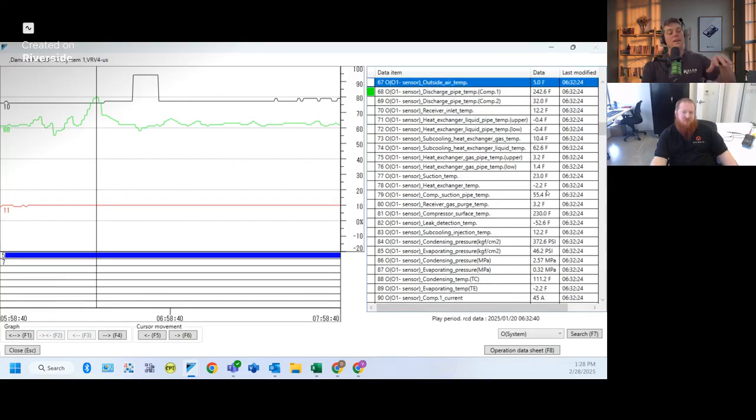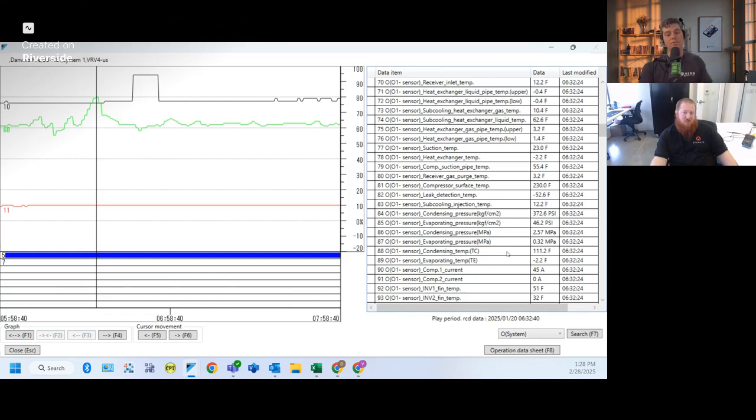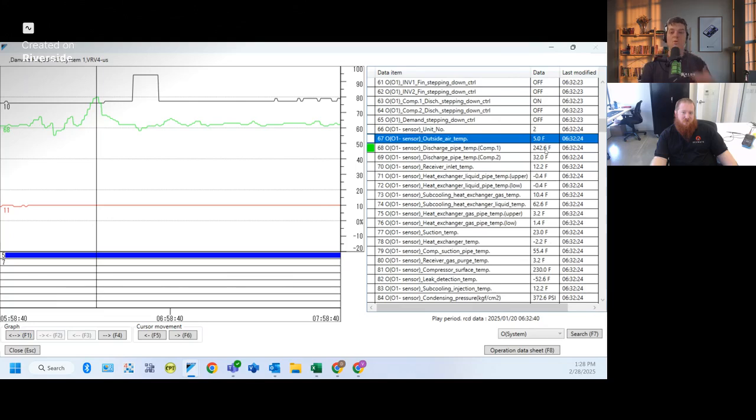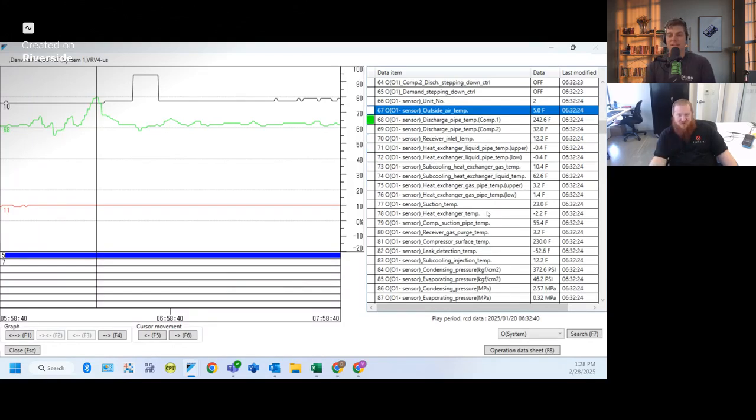But if your discharge temperatures are one thing, you can almost guarantee the internal compressor temperature is usually 30 degrees higher. And we know that POE oil begins to carbonize at 247 degrees, which tells me the oil in this compressor is toast. So if it doesn't die now and he fixes the problem, it's going to die eventually. It's on its way soon.